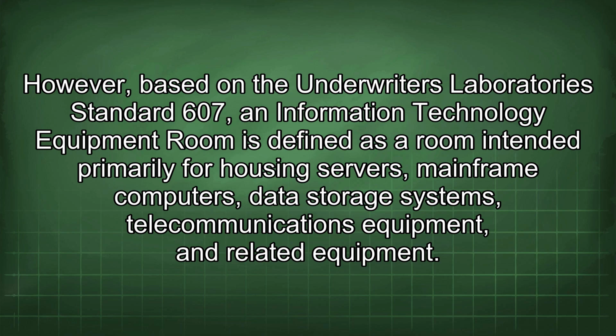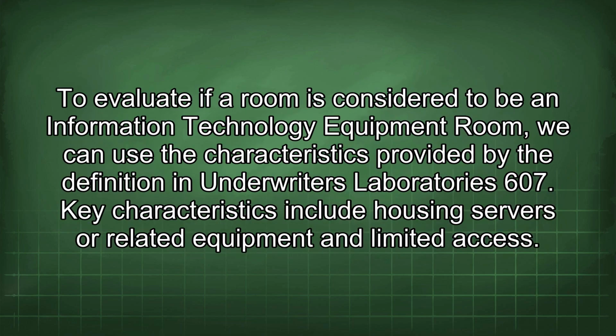However, based on the Underwriters Laboratories Standard 607, an information technology equipment room is defined as a room intended primarily for housing servers, mainframe computers, data storage systems, telecommunications equipment, and related equipment. To evaluate if a room is considered to be an information technology equipment room, we can use the characteristics provided by the definition in Underwriters Laboratories 607.